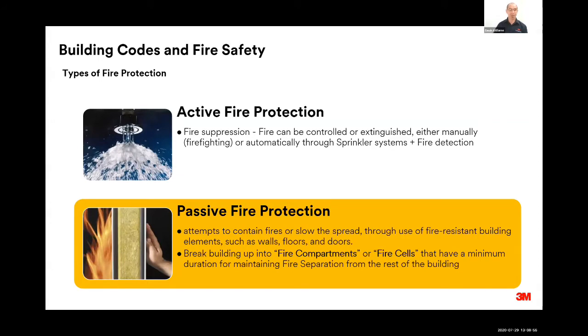Passive fire protection, however, is a method of constructing a building such that the various elements, the walls, the floors, doors, for example, are designed in such a way that the fire is slowed. So it doesn't fireproof, nothing's completely fireproof, but these elements give a duration through which fire will not pass. So in that way, we can create compartments or fire cells that give a duration of protection or separation.